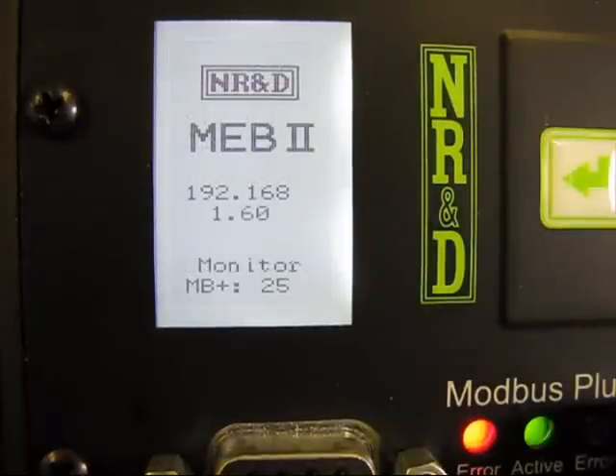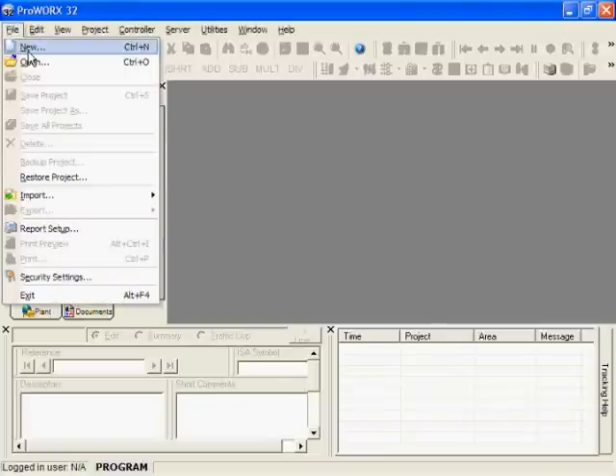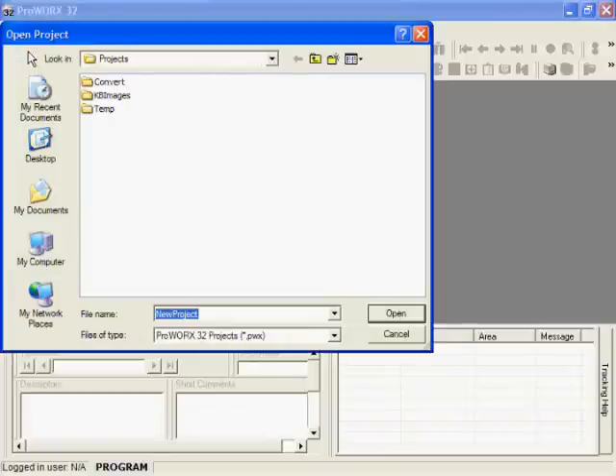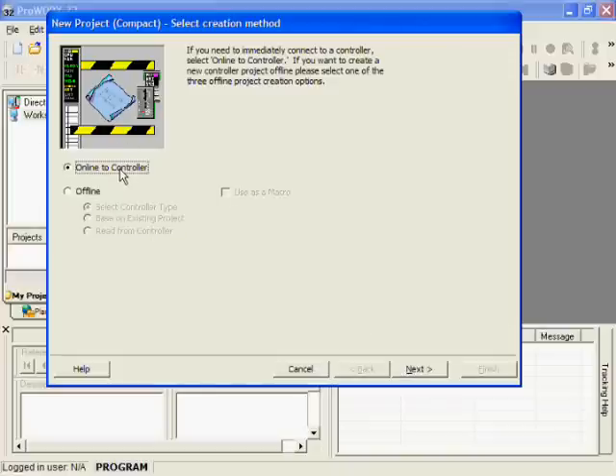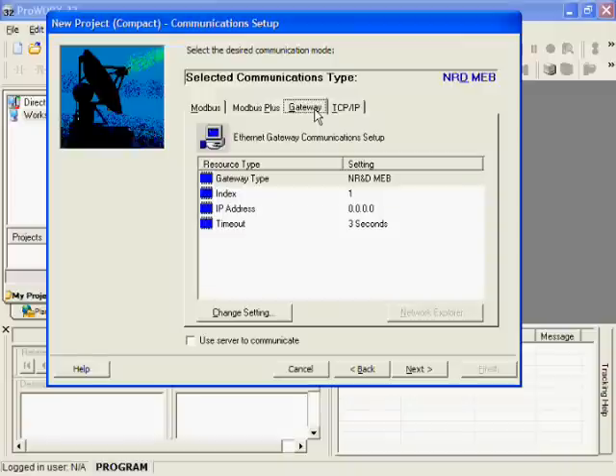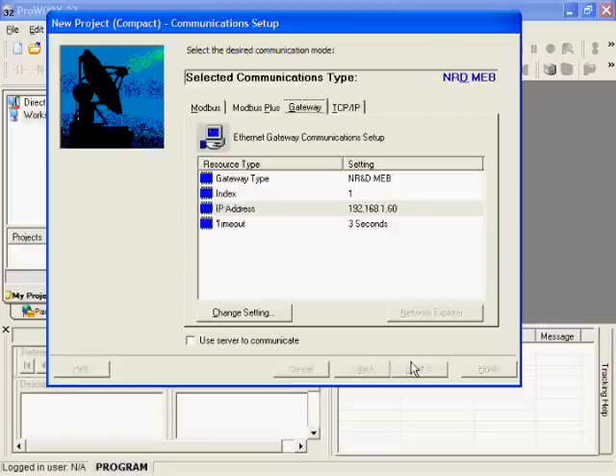OK, we are done. Now let's see it in action. We have an old Compact 984 at Modbus Plus drop one. Let's use ProWORX 32 to quickly connect to this PLC. Choose the gateway tab, set the IP address of the MEB2. In this case, the compact is at index 1, so just press finish to connect.